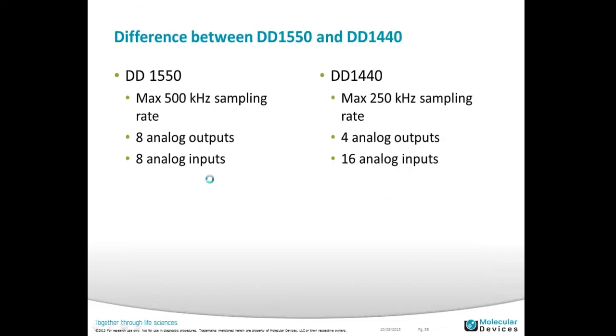Most people ask me what's the difference between the 1550 and the 1440. Basically, in the 1550 we increased the sampling rate up to 500 kilohertz, and we increased the analog output from 4 to 8. We found that a lot of people don't use 16 analog inputs, so we cut down to 8, which should be enough for almost 99% of electrophysiologists.